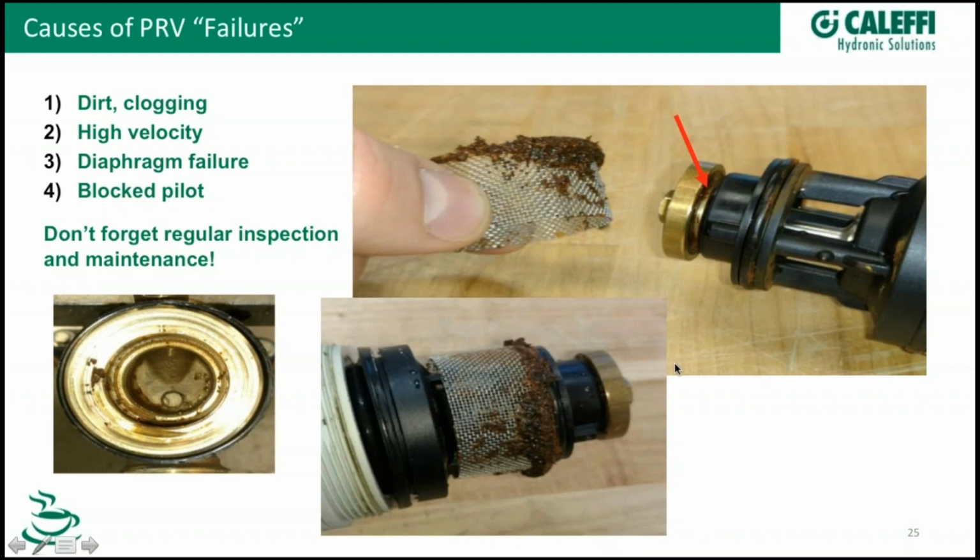So that's what I'll usually indicate. It's the indication of this is the pressure keeps increasing over what you've set the valve at. And that's a nice thing about the Caleffi with the gauge on it. That's exactly what that gauge can be used for, is troubleshooting.